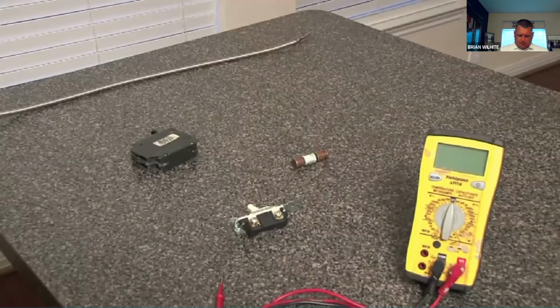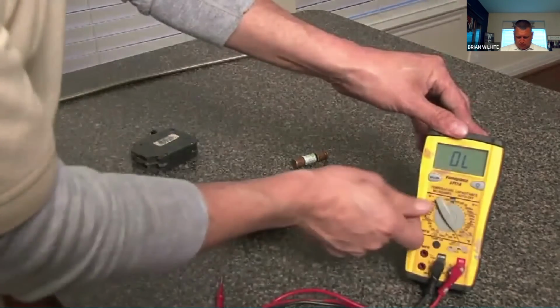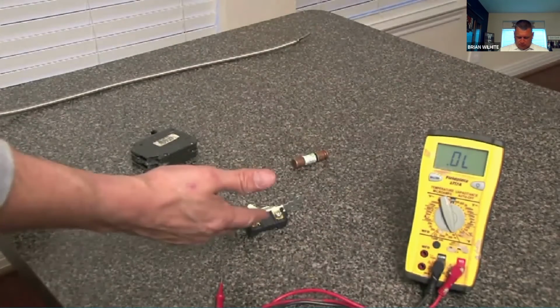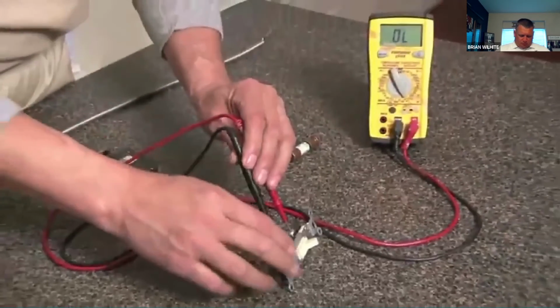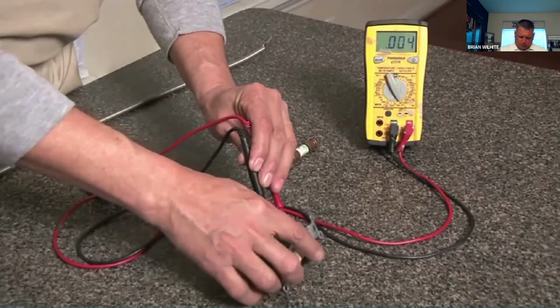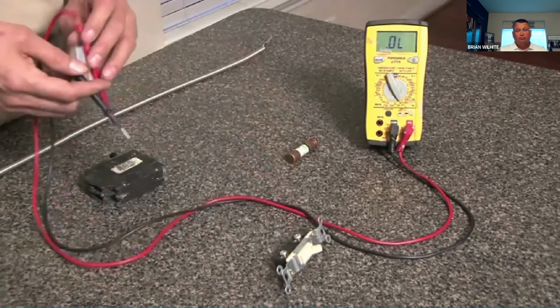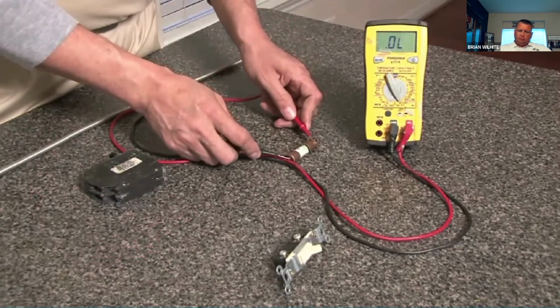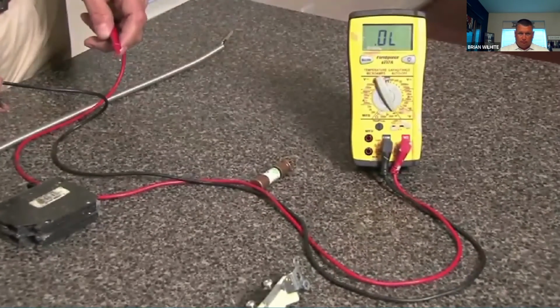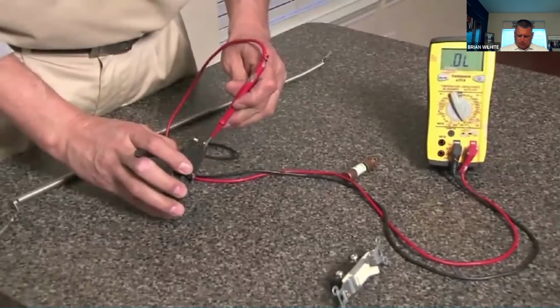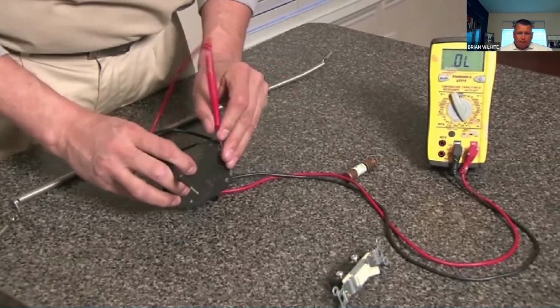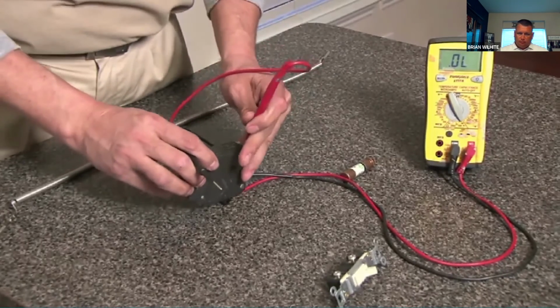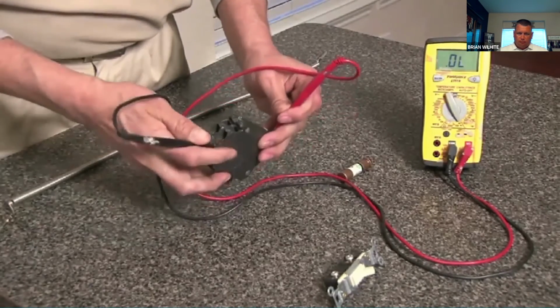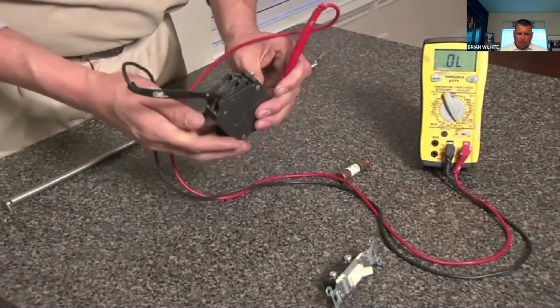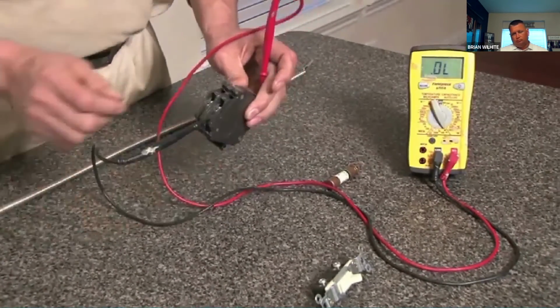Our technician is now going to show us how to check for continuity. He's going to use his meter, put it on the continuity setting. He's going to be checking a switch, a fuse, and a breaker for continuity. Our technician is going to show us how to check the switch for continuity. He's got the meter on continuity, turn the switch on. It's working, so the switch is good. I'm going to check the fuse for continuity. Check between the two terminals, and the fuse is good. Now he's going to check the breaker. He's going to put one side of the meter on the power coming into the breaker and the other side to the power going out of the breaker to check the breaker for continuity. And the breaker is good.